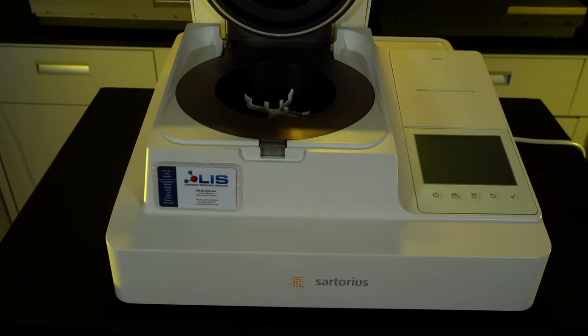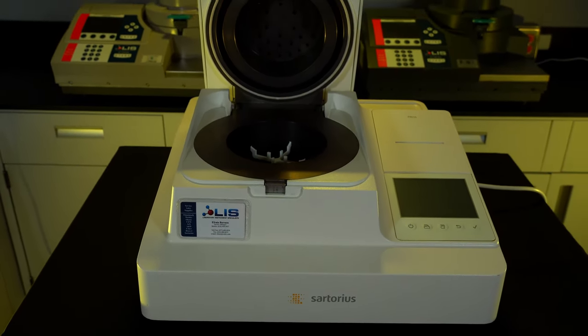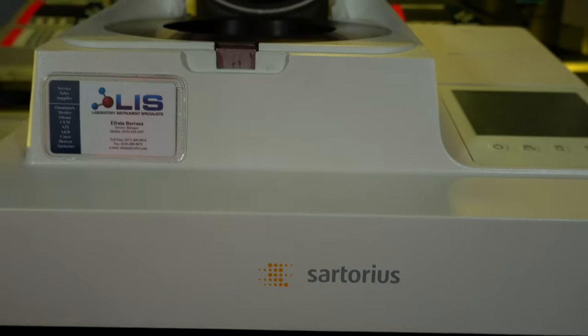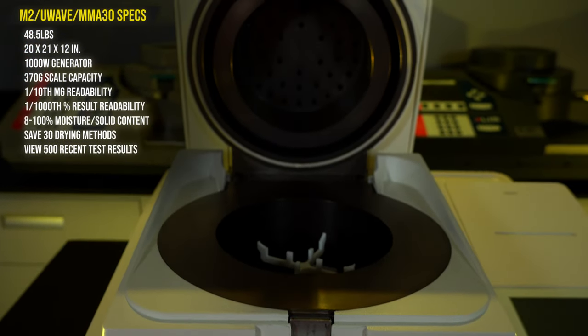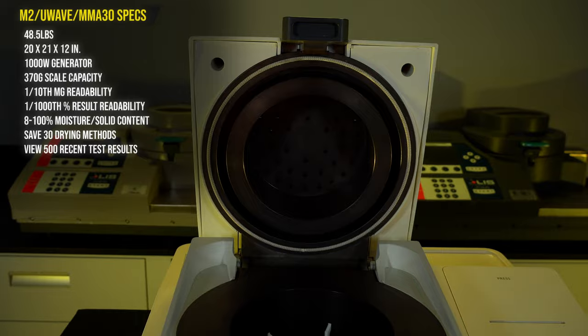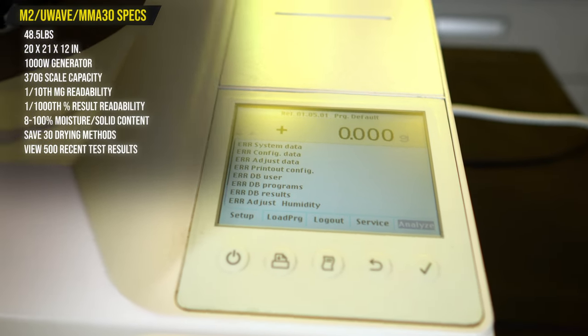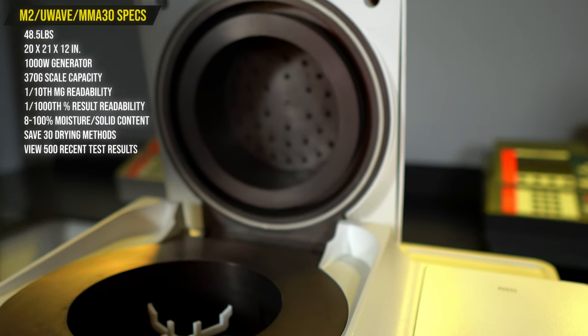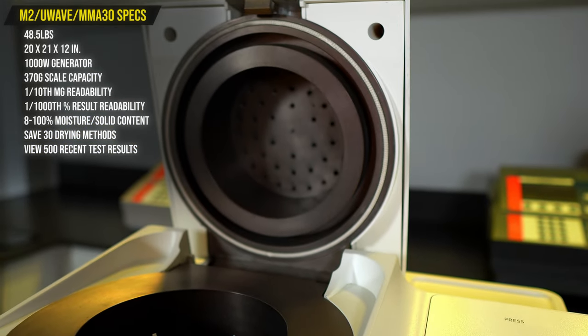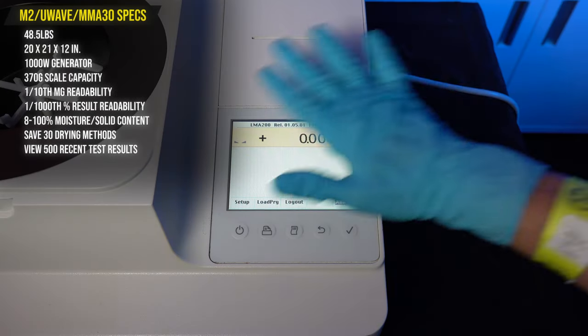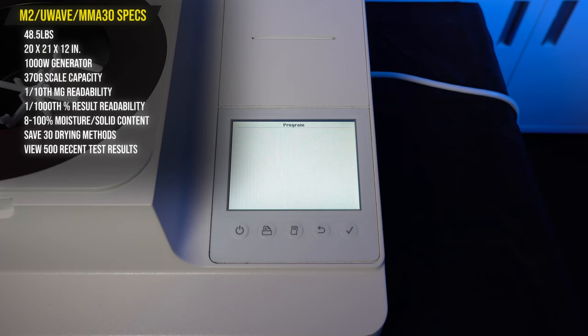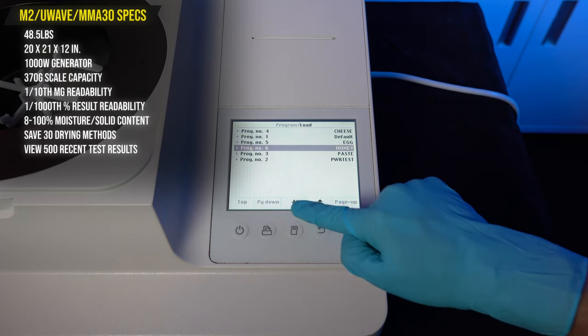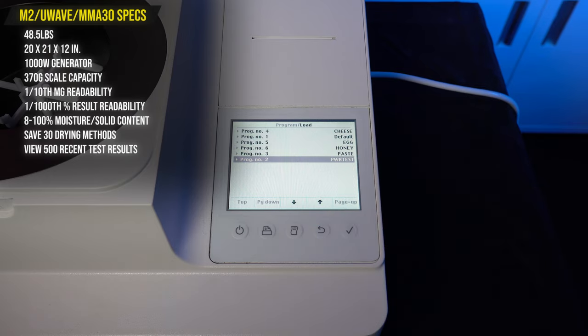We have yet to mention anything about the newer model that came out around 2010 called the LMA-200 that would replace the M2, U-Wave, and MMA-30. It's much lighter at 48.5 pounds and measures about the same at 20 by 21 by 12 inches. The instrument is heated by a 1,000-watt power generator. The maximum scale capacity is 370 grams and can read within one-tenth of a milligram. Testing results are very accurate with the readability within one-one-thousandth of a percentage while being able to determine between 8 and 100% of moisture or solid content. You can save up to 30 different drying programs and view up to 500 recent testing results.